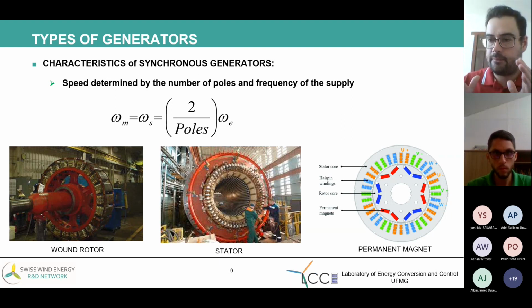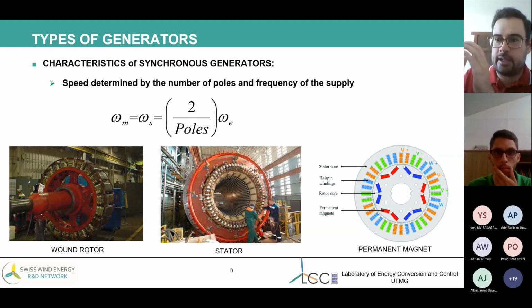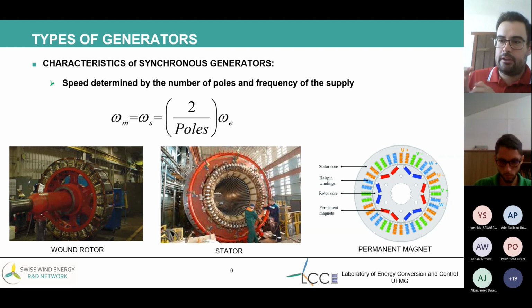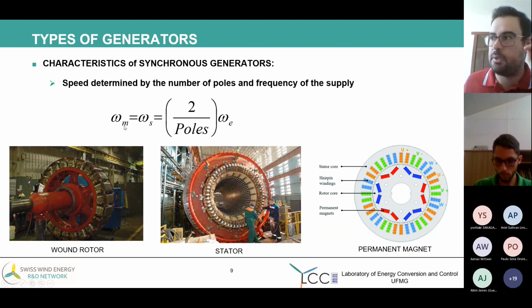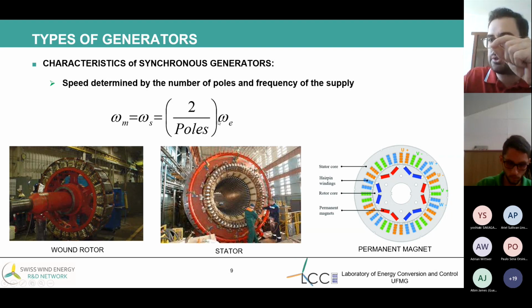As I said, the turbine speed, the rotational speed, is determined by the generator speed. For synchronous machines, the mechanical speed, the rotational speed, depends on the poles and the source that the generator is connected to.